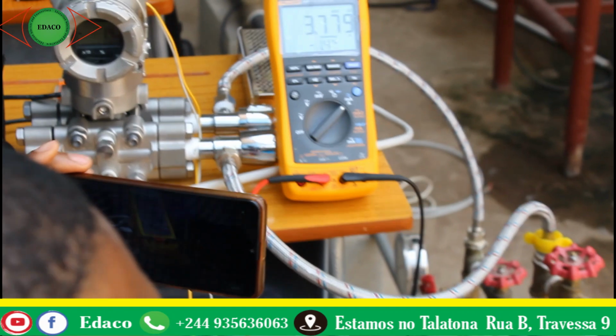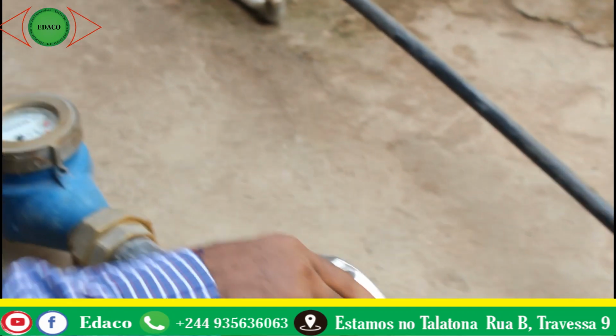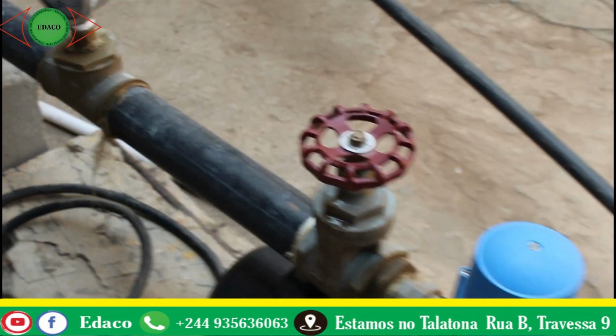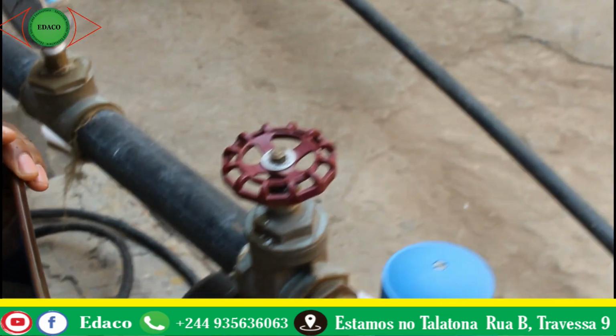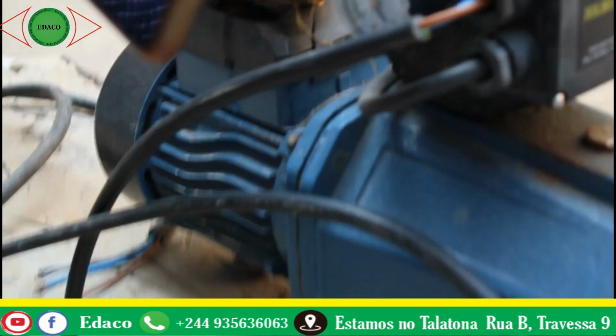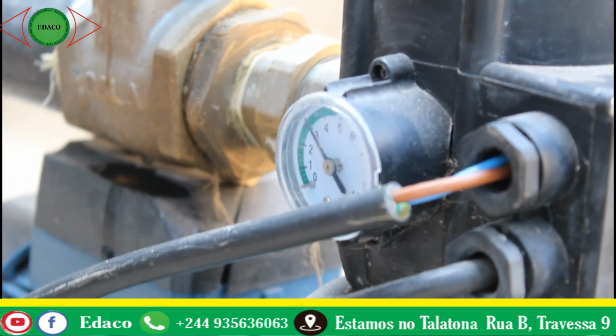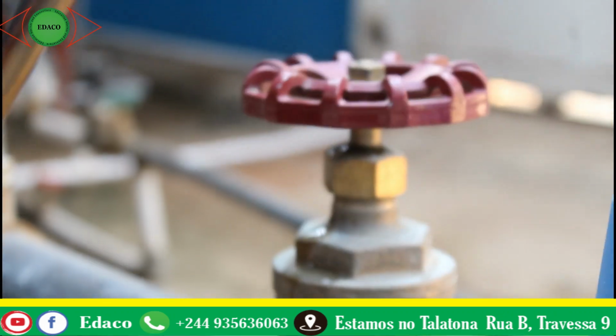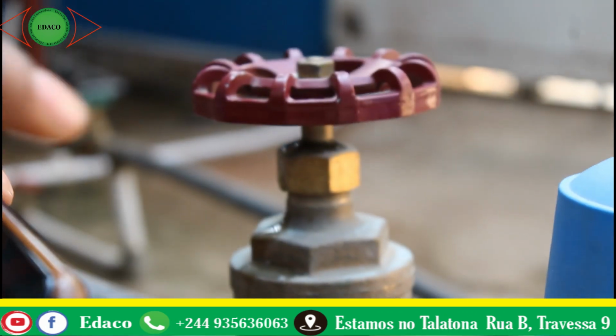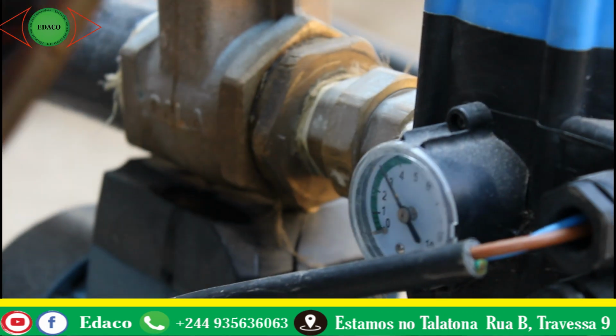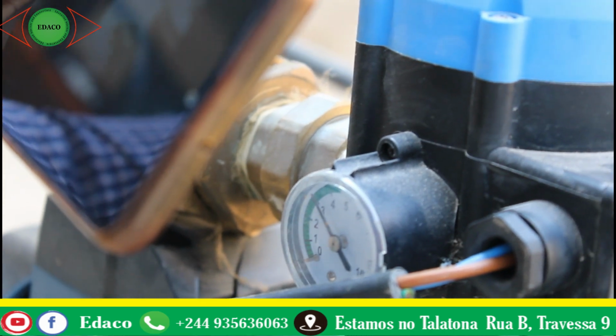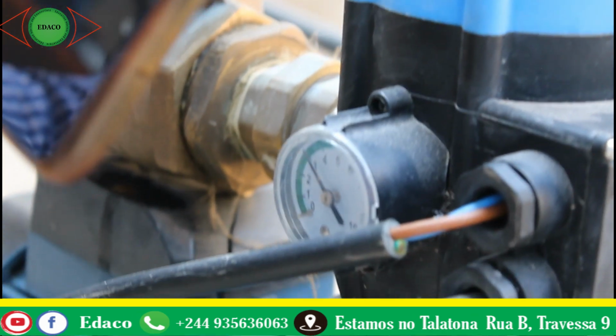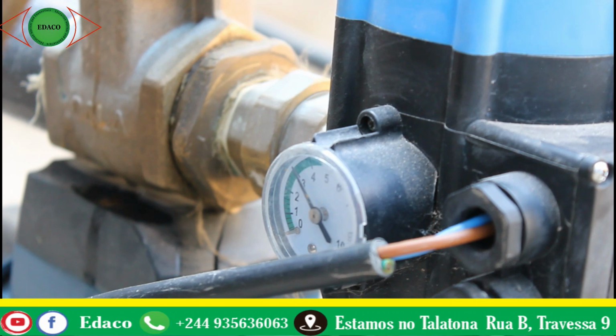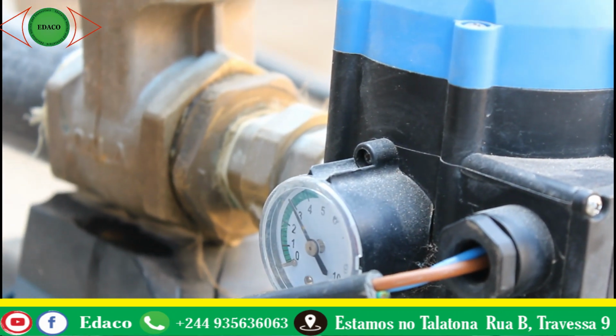So I'm going to start up the pump. I'm just going to open the valve. We have a pressure switch which controls our pump. Since I closed this hand valve, there was an increase in pressure to 3 bars, which is our set point to shut off the pump. So right now the pump is off because there is pressure.